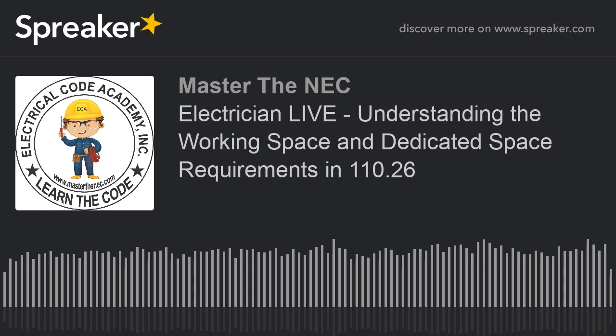Okay? Now, it goes on to say, control by automatic means shall not be permitted to control all illumination within the working space. Now, it can control some of the automation. We have very smart buildings these days, but it cannot control all of it. Okay, so motion, we don't want it to control, and I would say use a little common sense. The general illumination that's going to be for servicing of the equipment, that's the part I would not put on automation. Although the room might be big enough where you have other parts in it that would be controlled by some type of control automatic means, like motion.